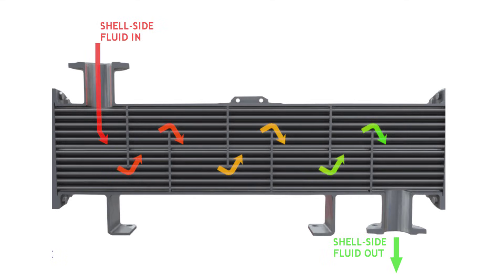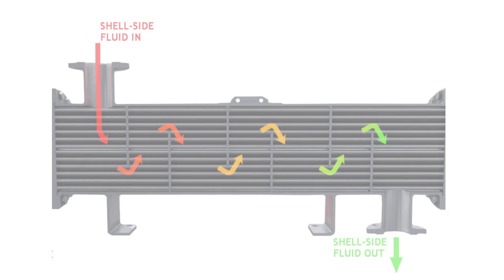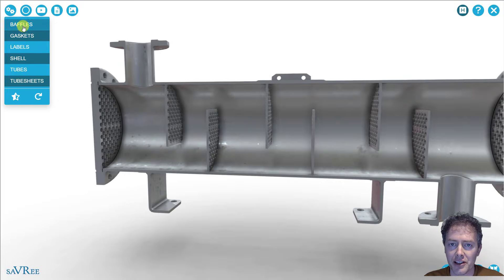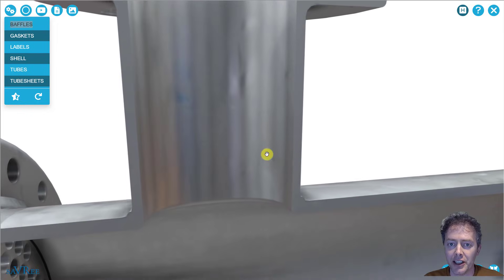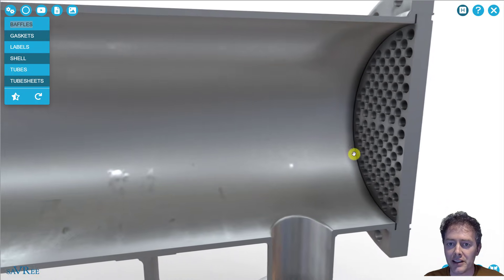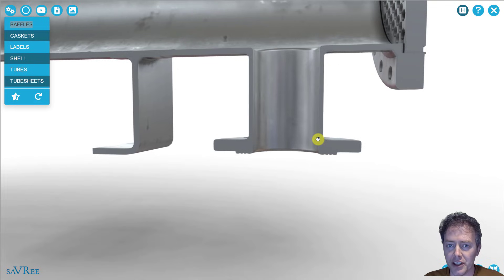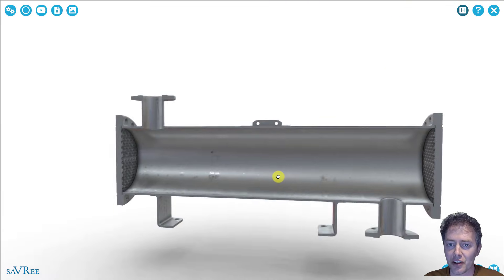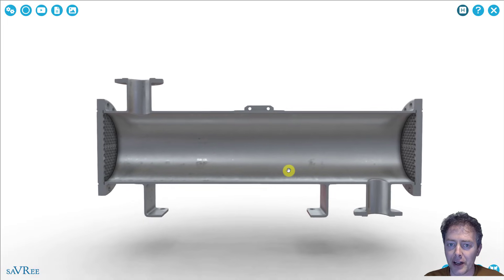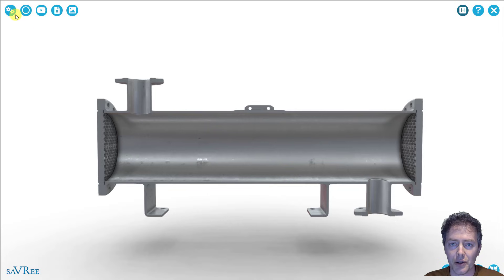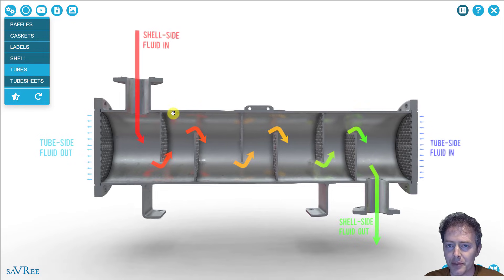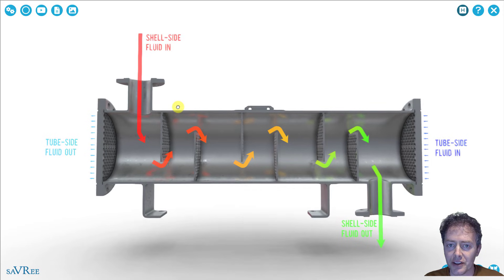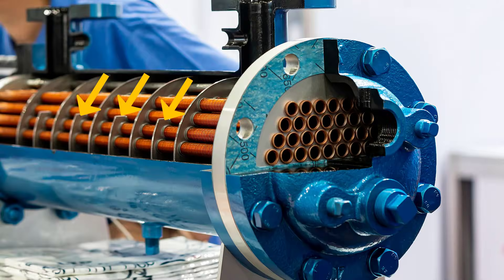This increases the heat exchange capacity of our heat exchanger. Without baffles, the shell fluid would come in and just go straight to the end of the heat exchanger and out through the discharge — only flowing a little bit over our tubes before exiting via the path of least resistance. So by installing the baffles, we ensure many changes of direction, and that change of direction is what pushes the shell side fluid over the tubes.